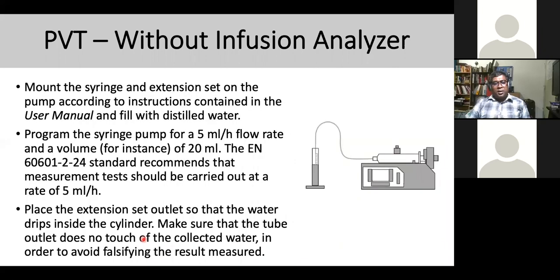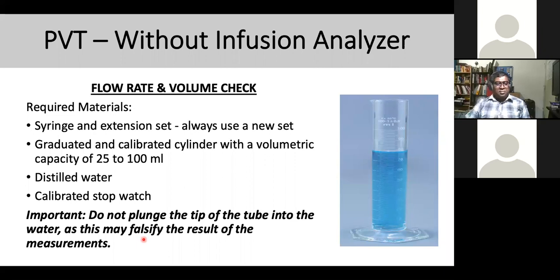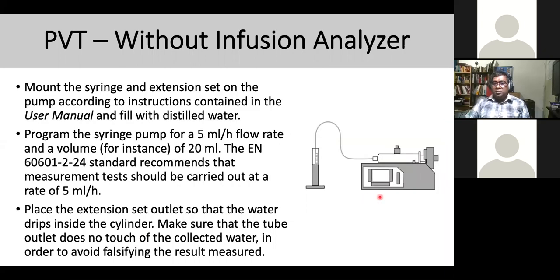And when you talk about testing, you need to follow this particular diagram. These are the syringe pump with the syringe and going to the cylinder. So the cylinder, when you set, for example, you program a syringe pump for 5 milliliter per hour and flow rate volume, for instance, of 20 ml according to the IEC standard. And you measure, carry out, the test should be carried out at a rate of 5 milliliter per hour.